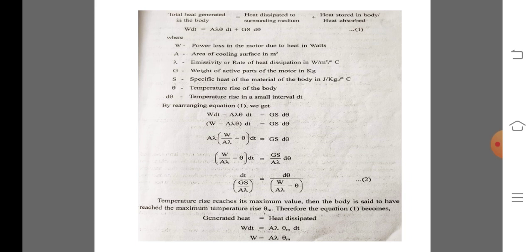Since the conductivities of various materials do not differ by a large amount, a simple thermal model of the machine can be obtained by assuming the machine to be a homogeneous body. Although inaccurate, such a model is good enough for the drive engineer, whose job is only to select the motor rating for a given application, ensuring that temperatures in various parts of the motor body do not exceed the safe limits.